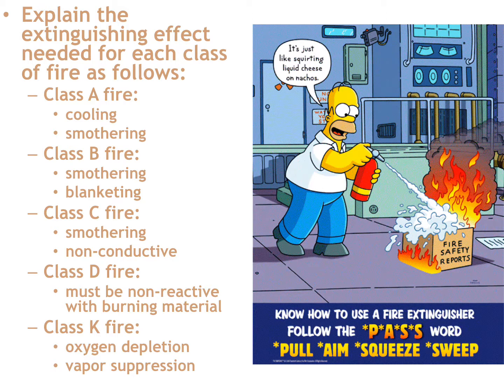For a Class C fire with a CO2 extinguisher, the CO2 does a couple of things. First, the big white cloud from the extinguisher envelops the burning object and displaces oxygen from the area, helping extinguish the fire. Additionally, the CO2 itself is very cold, so you get rapid cooling of the object as well. Another benefit is that CO2 is non-conductive, so regardless of how much electricity is flowing into the burning equipment, the CO2 extinguisher won't conduct electricity and electrocute you.